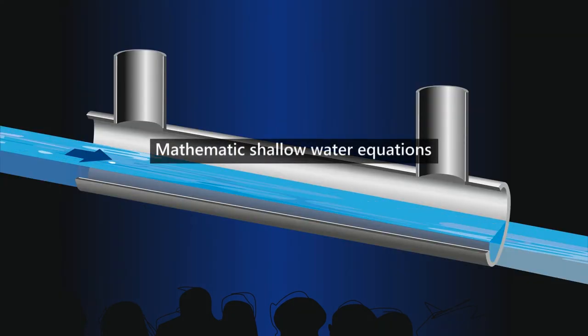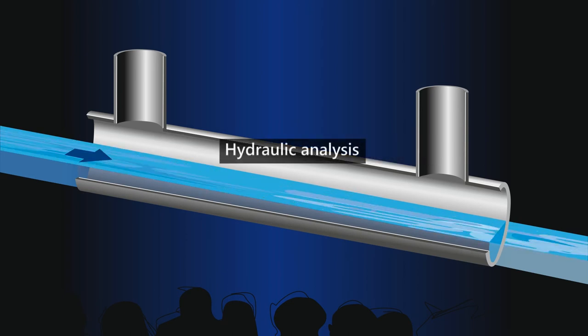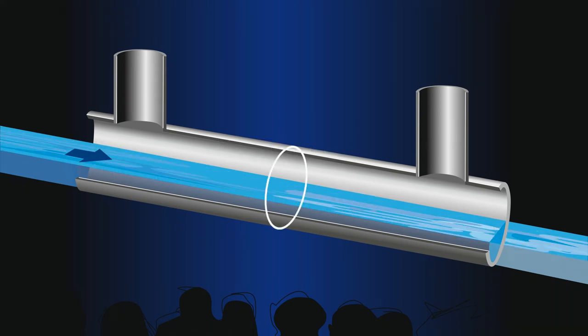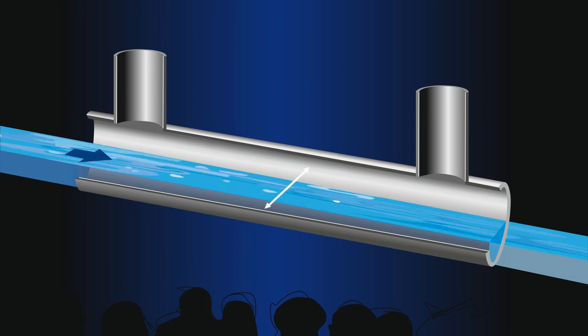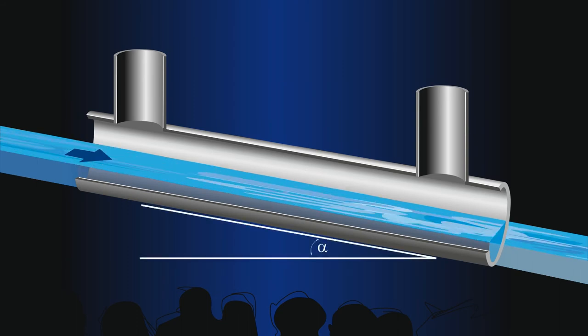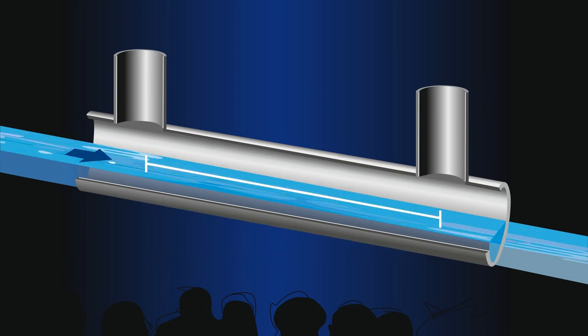The NIVUS system is based on the mathematic shallow water equations. To perform a hydraulic analysis, first, the geometric features of the measurement point are determined: shape and dimensions of the canal, the slope, as well as the accurate distance between two level measurement points.